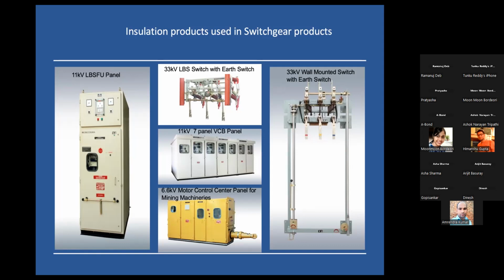is with epoxy, as already mentioned earlier, it can be used only in indoor applications primarily. The reason is that epoxy reacts with UV rays and the properties get deteriorated. To combat that, nowadays new systems have come into the market, and these resin systems are called cycloaliphatic resins, and also non-hygroscopic resins. These prevent the deterioration and are used outside for outdoor applications also. Unfortunately, the cost is prohibitively high and people are not going for it on a mass scale, though it is coming in.